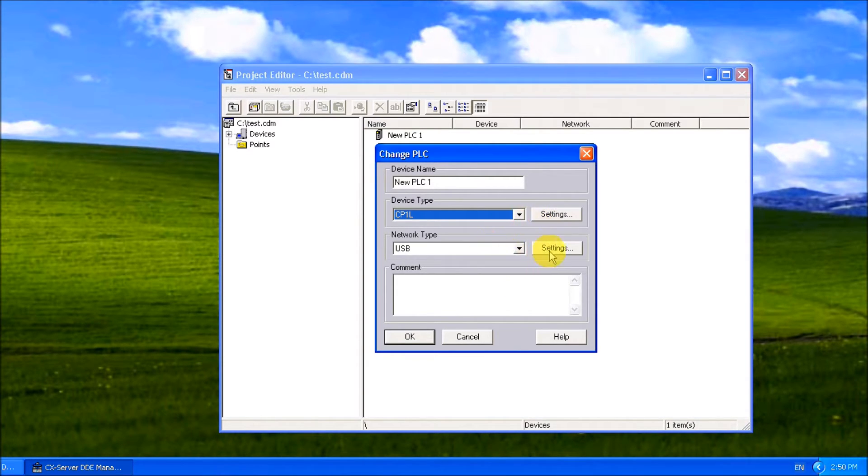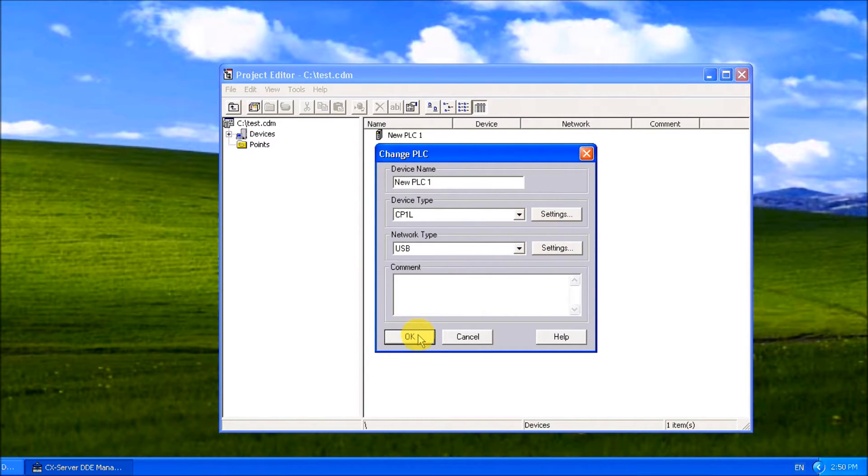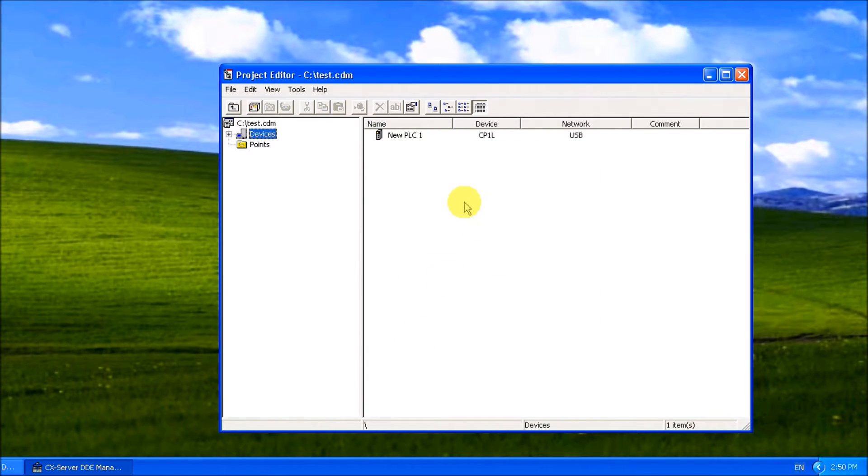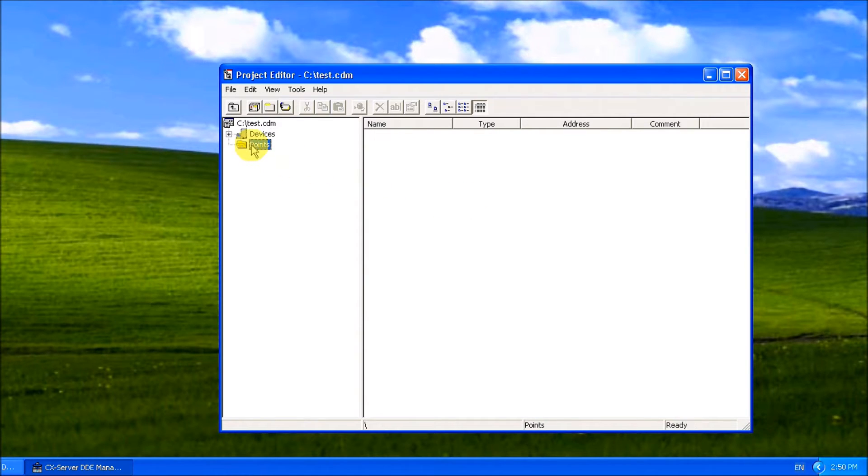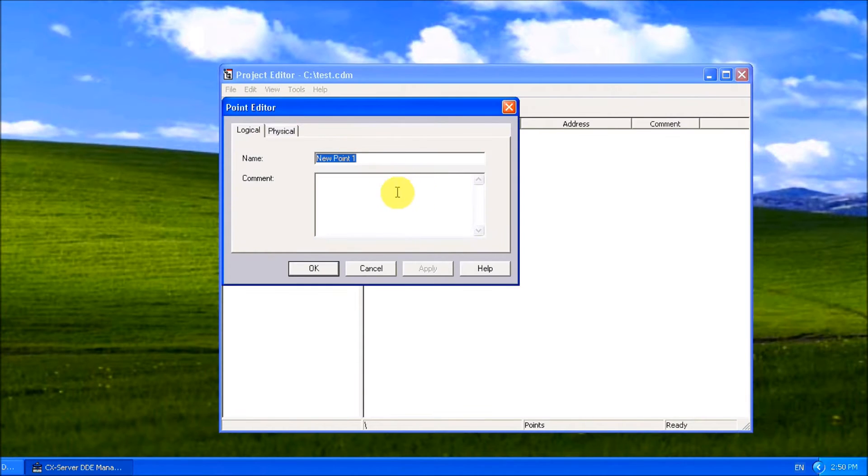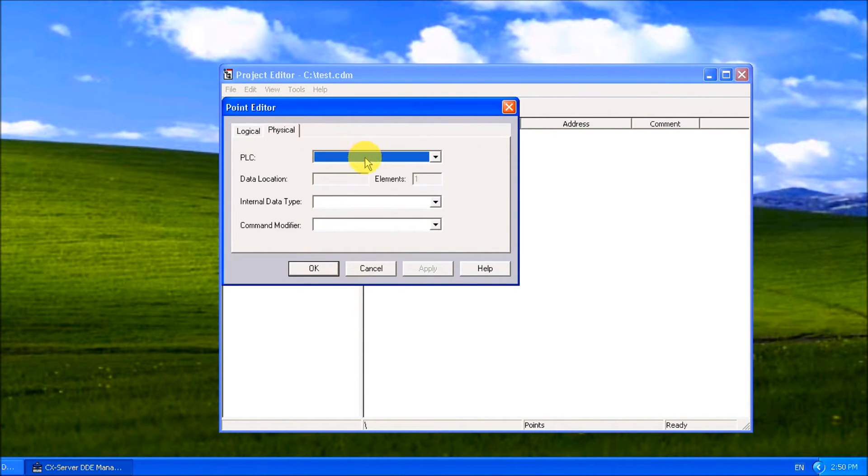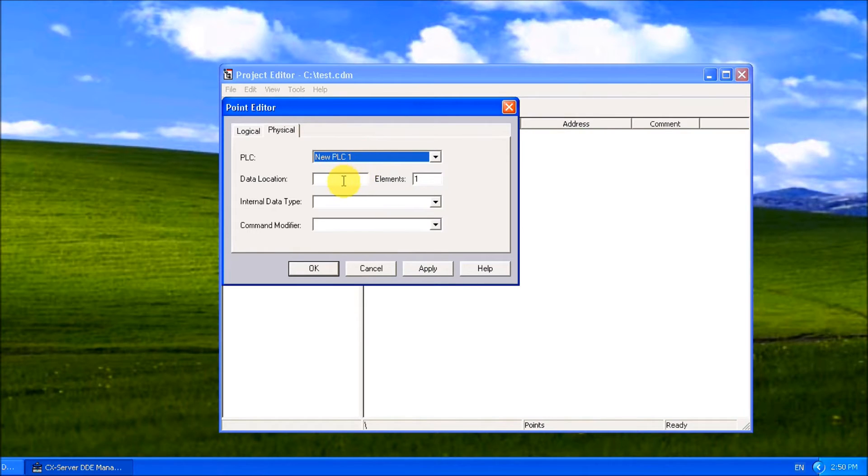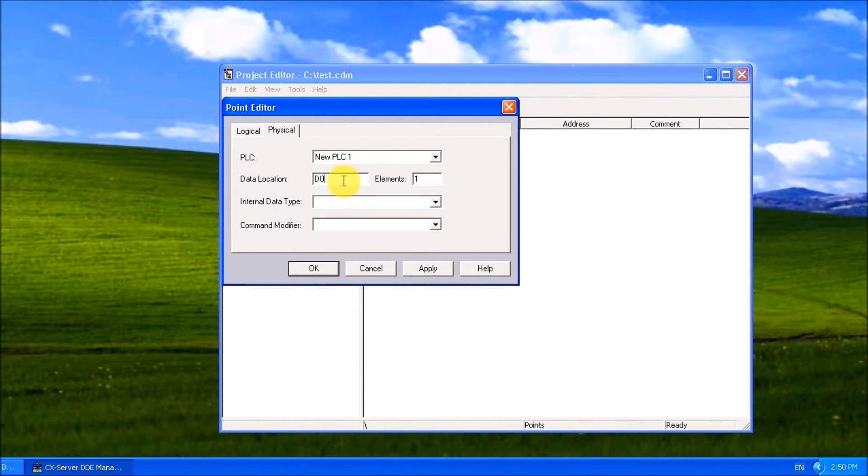The settings is going to be USB. Hit okay, and you'll see this new PLC 1 come up with the device CP 1L. Now go to points, add point. This is the logical name, then go to physical and add the new PLC 1. Our data will be at DM 0.